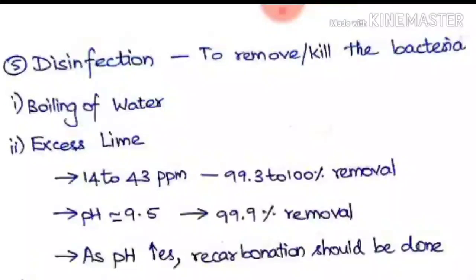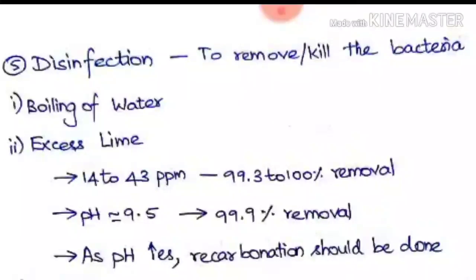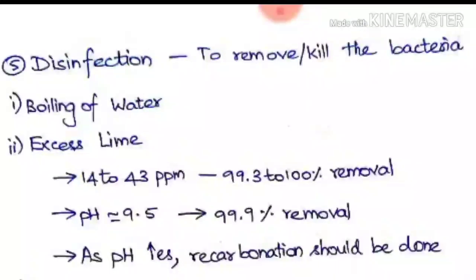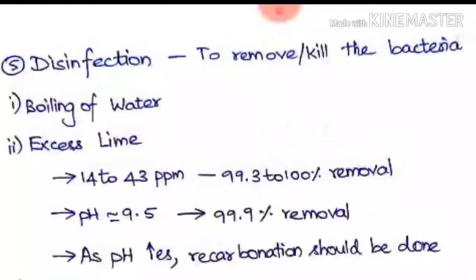The first minor method is boiling of water. If you just boil the water, the bacteria will be killed, but it cannot be used on a large scale. The next is excess lime. When excess lime is added to the water at nearly 14 to 43 ppm, nearly 99.3 to 100% removal of bacteria is possible, but the main problem is that the pH will be increased.